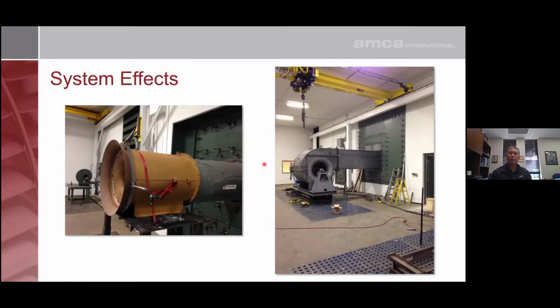Well, when we look at how a fan is tested, here we have an inline fan, here we have a centrifugal fan. Both fans have open inlets and they have a bell mouth at the inlet. The bell mouth guides the air into the fan uniformly, and we eliminate entry losses into the fan over a sharp-edged orifice. Discharge-wise, there is a straight run of ductwork leading out of the fan into the test chamber. And that ductwork allows for the velocity profile of the air to even out. If we have a situation where that installation is different than this installation, that fan may perform differently. There are some ways to make the fan perform better, and some ways to make the fan perform much worse.